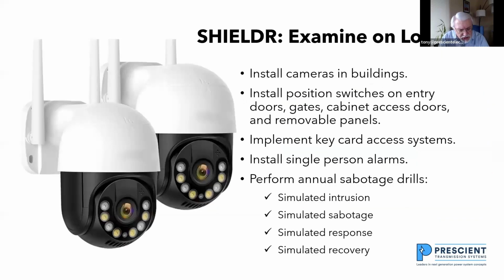When I talk about examining on location, the first is installing cameras in buildings so you'll have an awareness of who's on site. And then you want to install position switches on doors and cabinets, access panels, gates, so that when someone opens a cabinet or opens a panel, they've already alerted security that they're going to do that. If someone opens it and they haven't alerted security, then security is going to come out and ask, like, what are you doing out here? So we're going to implement key card access systems. And the key card access systems would be actually within the station. So if you use your card to get into a substation, then you use your card to get into a transformer bay, you use your card to get out of the transformer bay, and then use your card to leave the station.